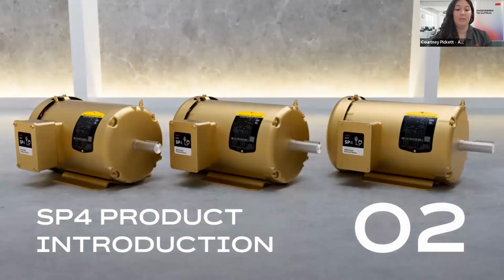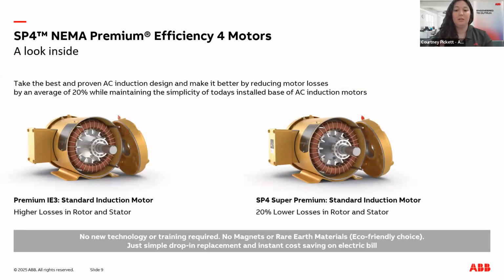Now that we've seen why efficiency matters, let's talk about how to achieve it. I'd like to introduce you to ABB's SP4 motor platform. A lot of facilities will typically stick with the older motors because upgrades can seem risky. There are new technologies, retraining, compatibility concerns. It all feels like more trouble than it's worth. But that's exactly why we developed the SP4. It's a drop-in, no-compromise solution built around the same AC induction motor technology that you're already using. It's a familiar, just better motor. SP4 reduces your motor losses by 20% on average with no rare earth metals, no new training, and no surprises. Just a smarter motor ready to install and start saving.